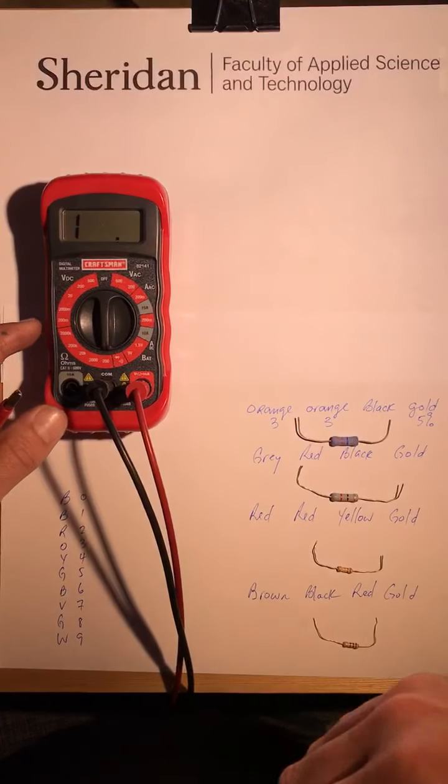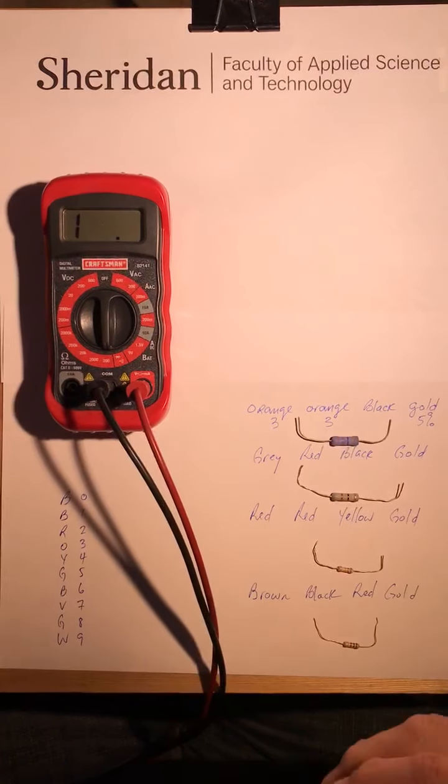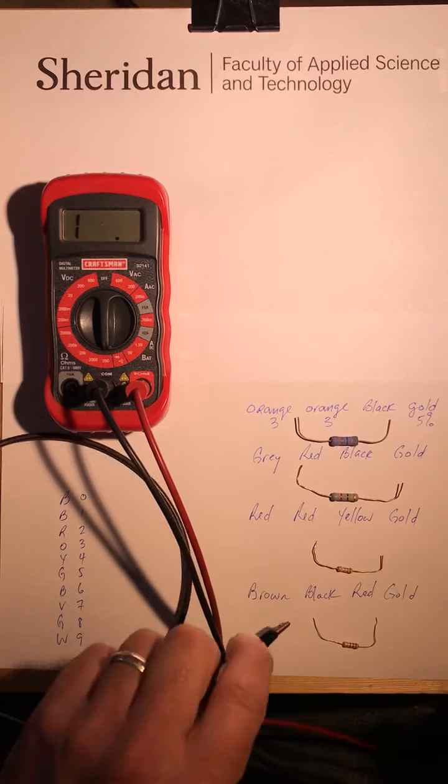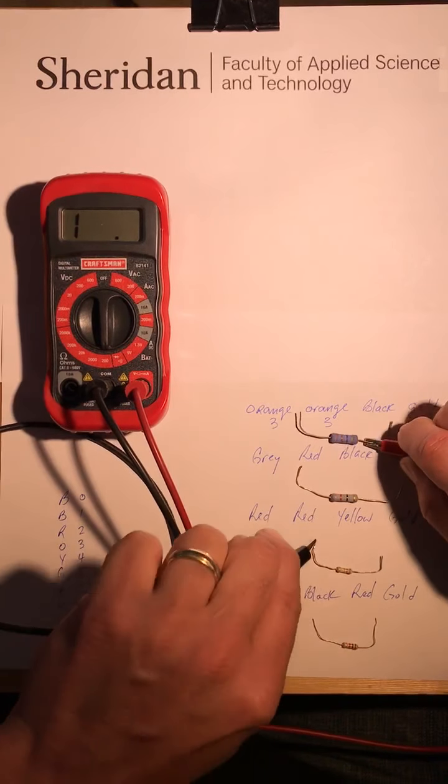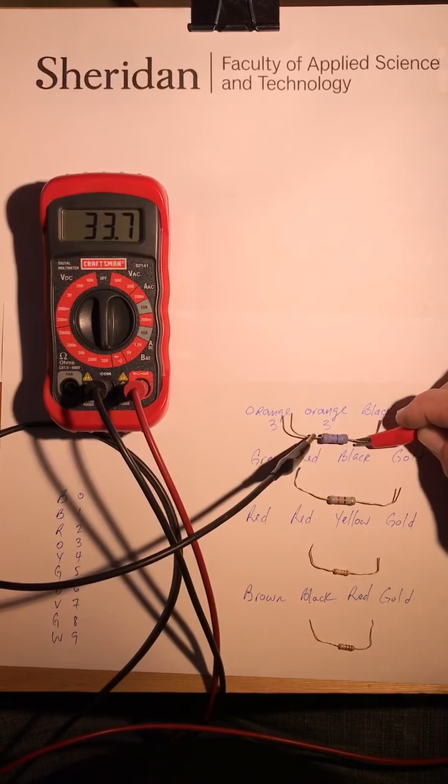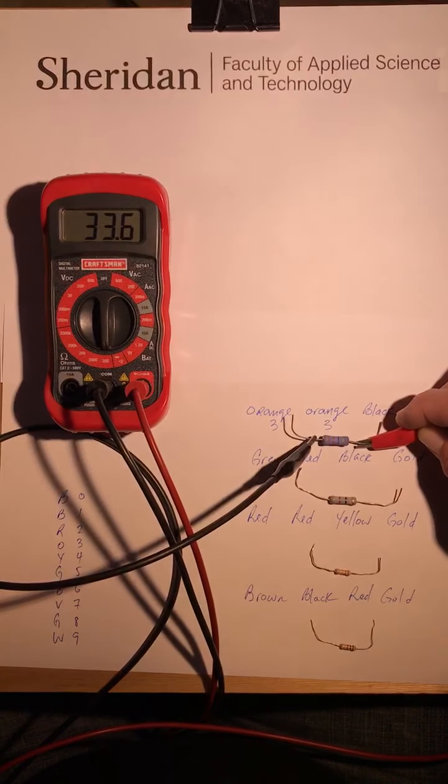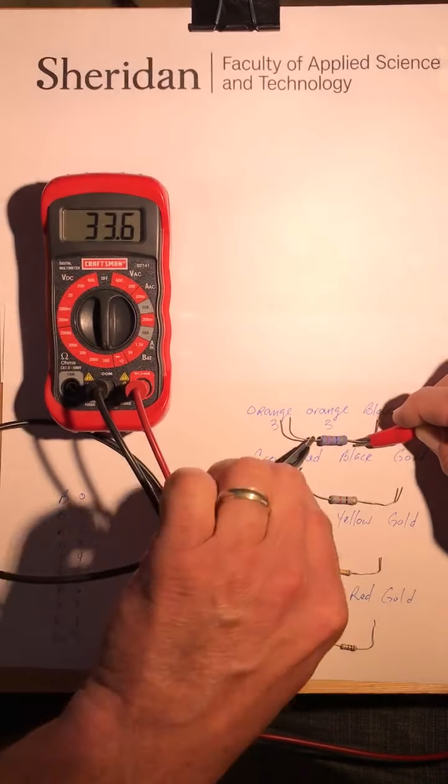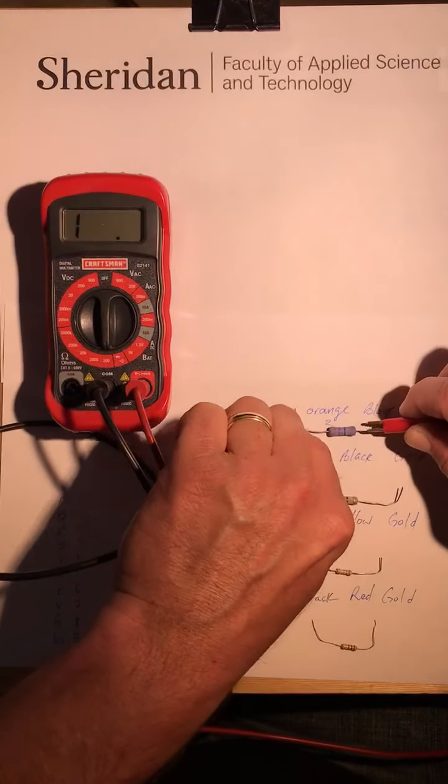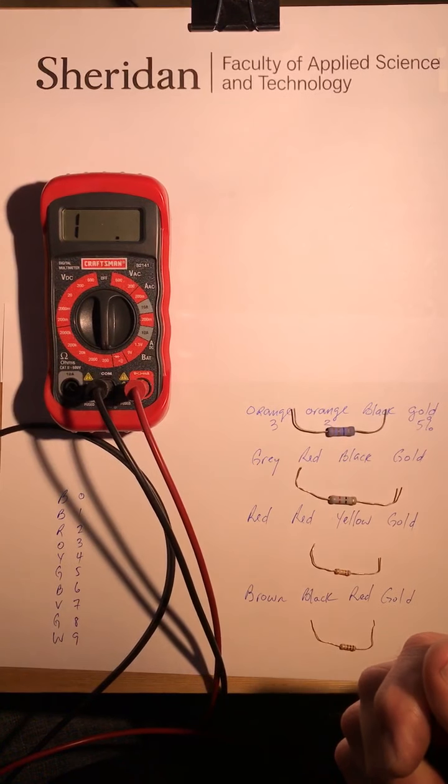So if I take a look at this one here, I put that across there and there. I'm supposed to be within five percent of 33, so we're good - it's showing up as 33.6. Notice how I keep my fingers off of it, because if I add my fingers to it, then I'm gonna add a value of resistance - my own resistance - so I don't want to do that.